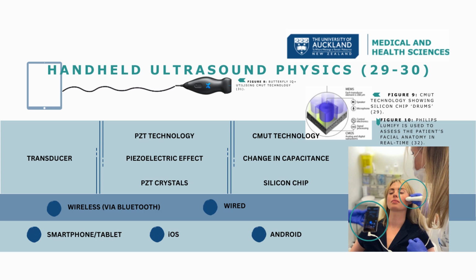Other probes, such as the Butterfly IQ Plus, have a silicon semiconductor sensor chip, which contains a 2D array of capacitive micro-machined ultrasound transducers, or CMUT. This is similar to an array of silicon drums, each of 208 microns, with a speaker and a microphone that vibrates when voltages are applied. When echoes are received, there is a change in capacitance, which is then converted to electrical signals.